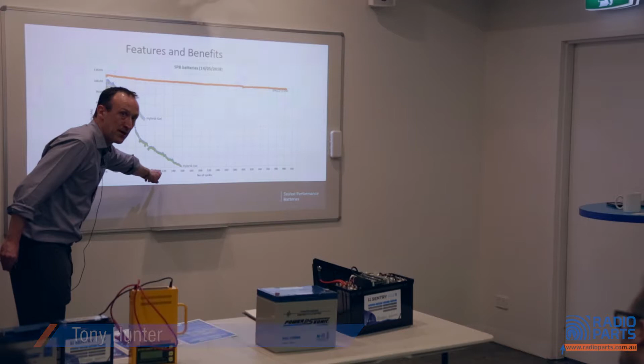If we take into account this point here, and we get to, say, 100 cycles, you realise that after 100 cycles being drained all the way down, now, you know what? Ideally, when you're draining a lead acid battery, the optimum, or the recommended depth of discharge is 30%. I used 50% as a point of reference before, but 30% and you'll do well.